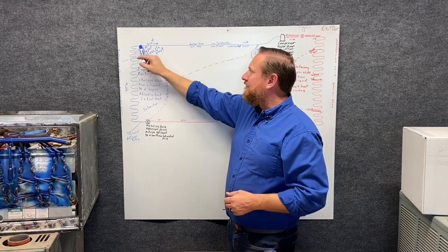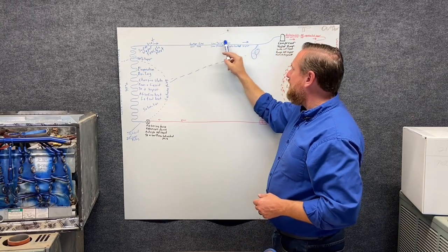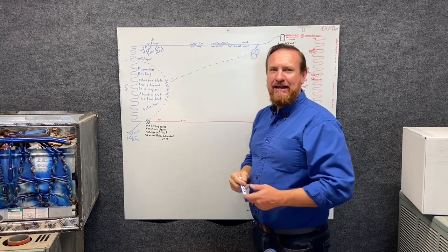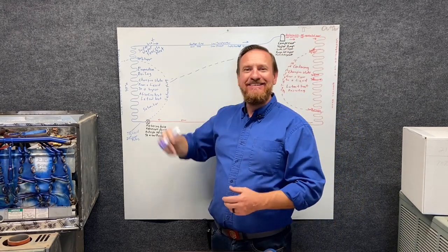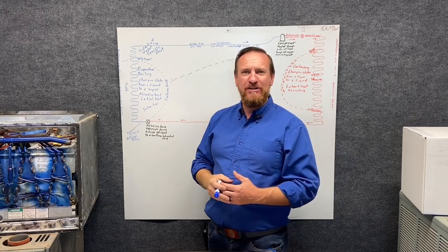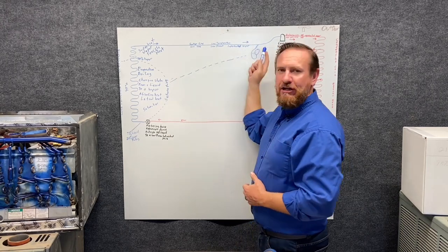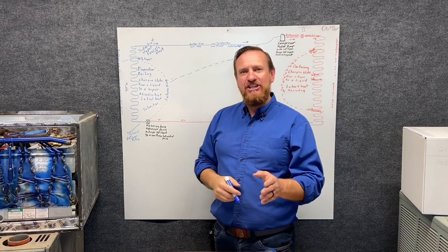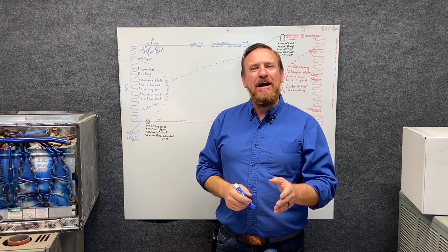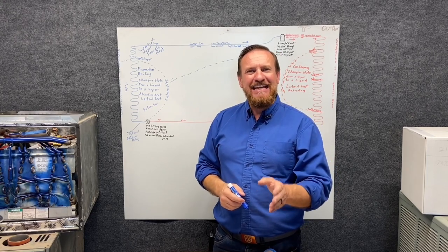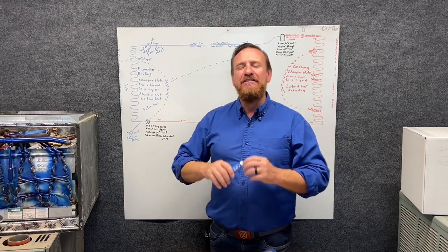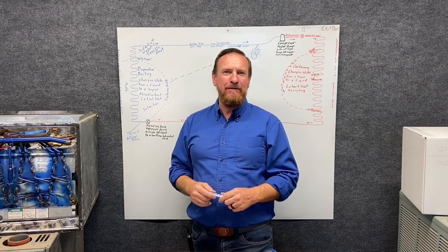So now, say I'm 45, 46, 47, 48, 49, 50, 51, 52, I can add heat all the way back to the compressor, which is why this line is insulated. This line's insulated because we don't want to be absorbing any extra heat, but I can simply measure my superheat. So the definition of superheat, and write this down, the definition of superheat is the amount of sensible heat added to a vapor above saturation. Superheat, the amount of sensible heat added to a vapor above saturation.